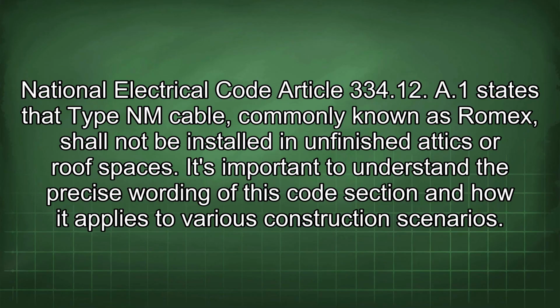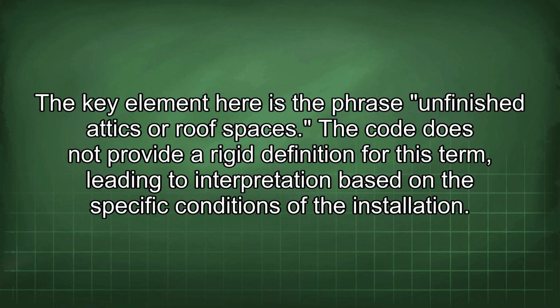National Electrical Code Article 334.12 states that Type NM cable, commonly known as Romex, shall not be installed in unfinished attics or roof spaces. It's important to understand the precise wording of this code section and how it applies to various construction scenarios. The key element here is the phrase unfinished attics or roof spaces.